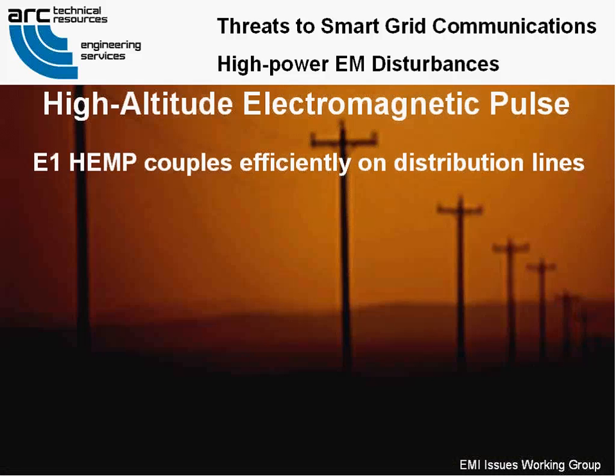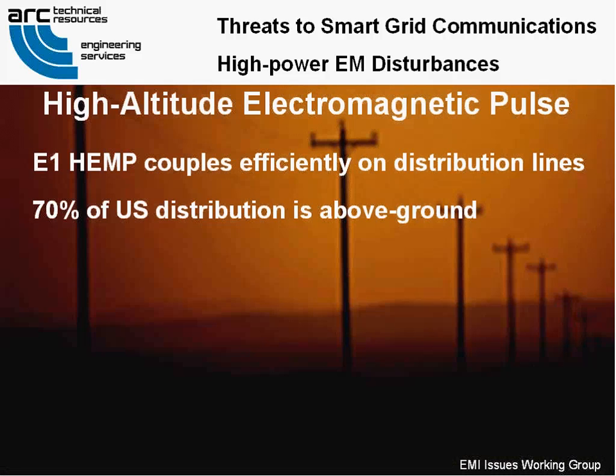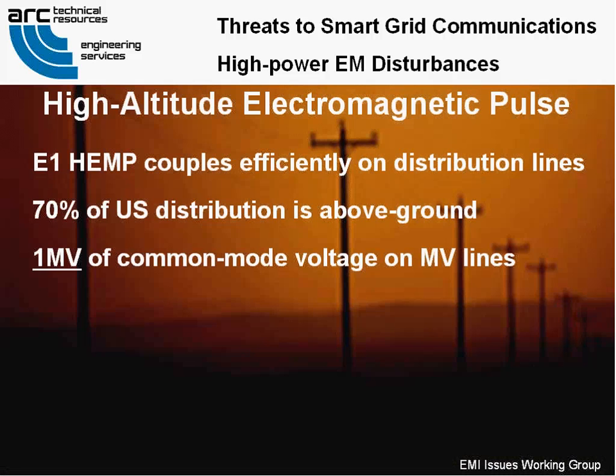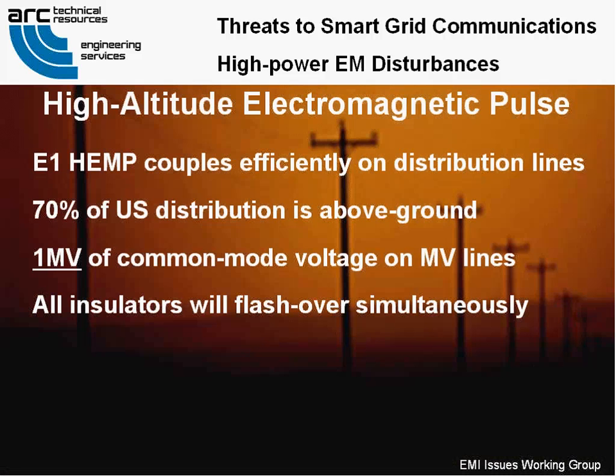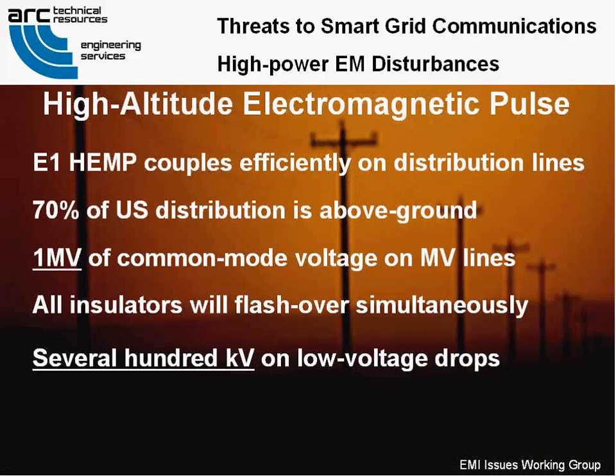E1 HEMP will also couple efficiently onto above-ground distribution lines and low-voltage drops into homes and businesses. 70% of U.S. distribution wiring is above ground, which can experience up to 1 megavolt of common mode voltage with a 10 nanosecond rise time and 100 nanosecond duration. All insulators will flash over simultaneously, causing mechanical damage to some of them and allowing up to several hundred kV of voltage onto the low voltage drops, probably frying the smart meters.